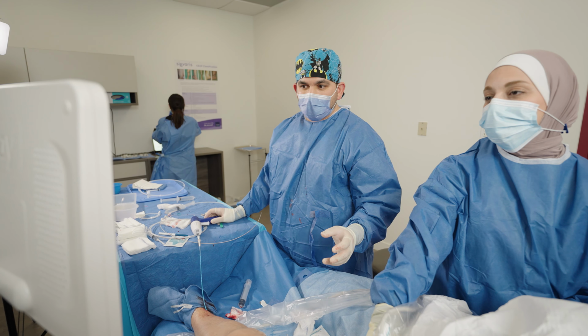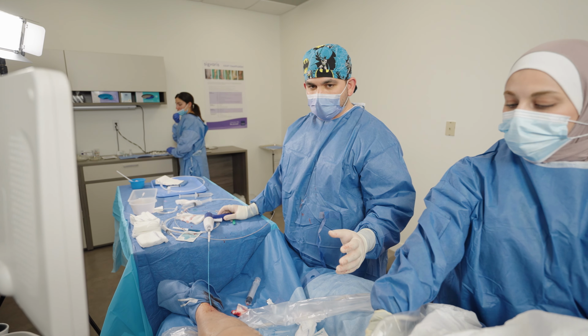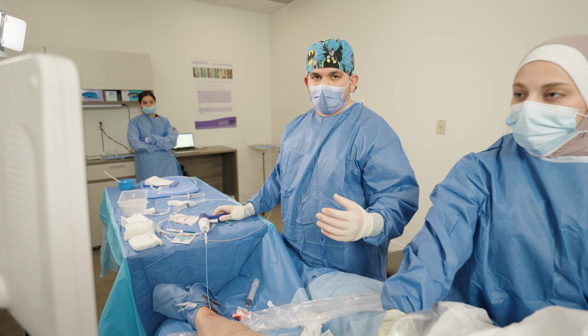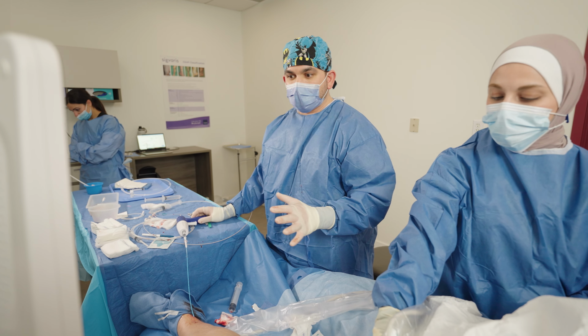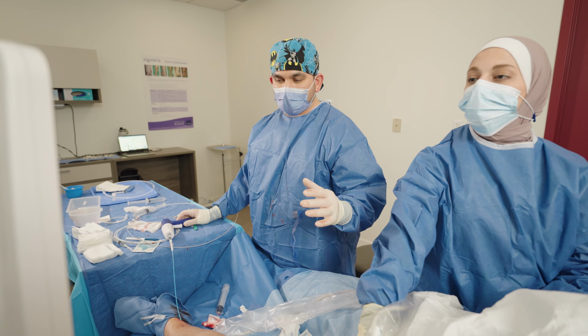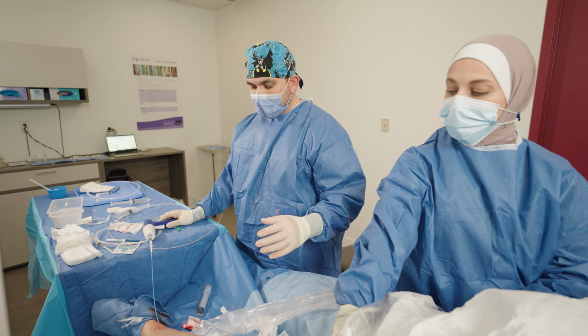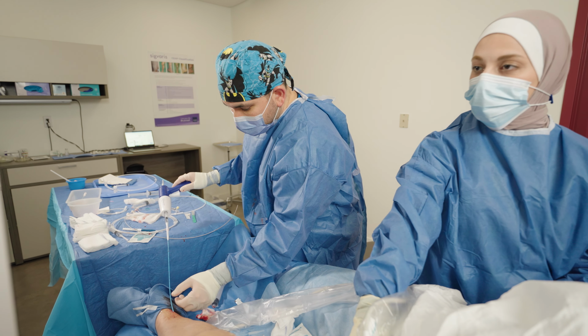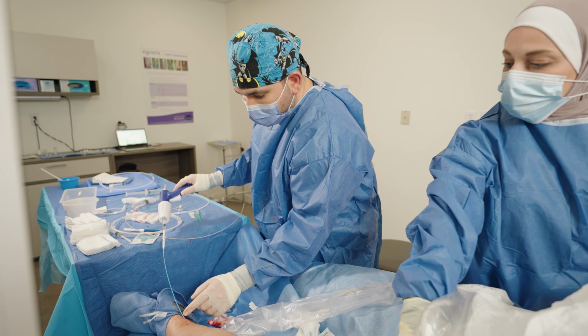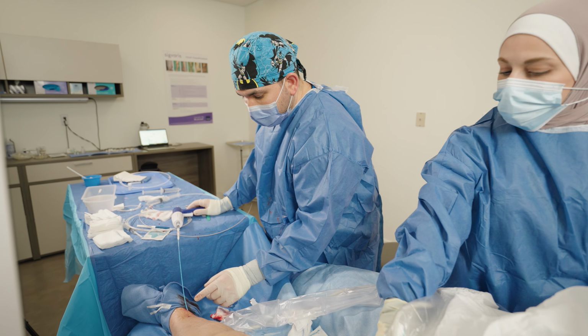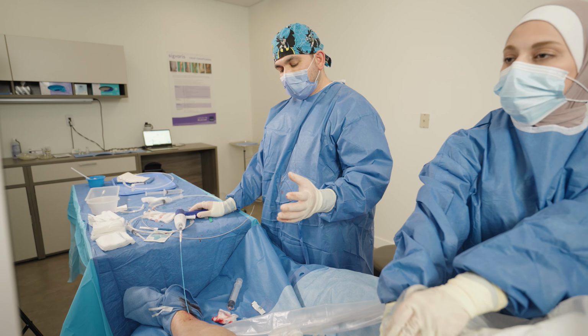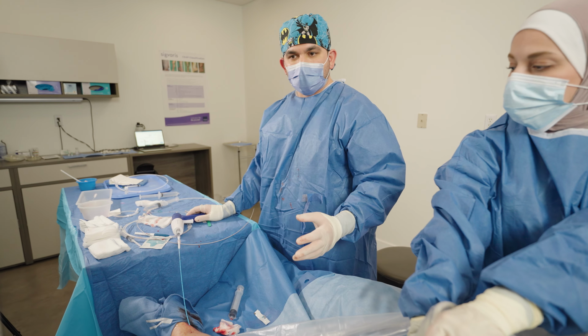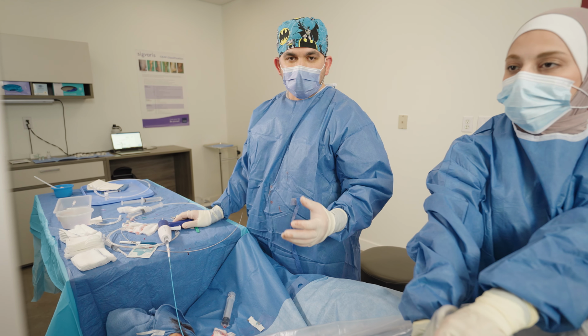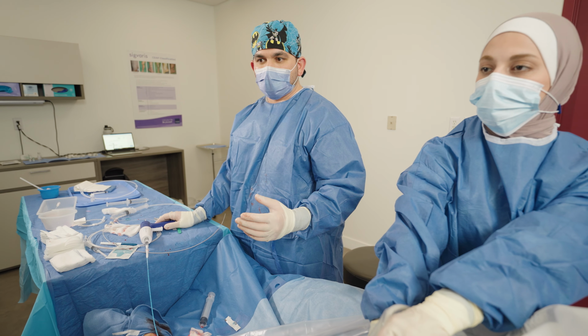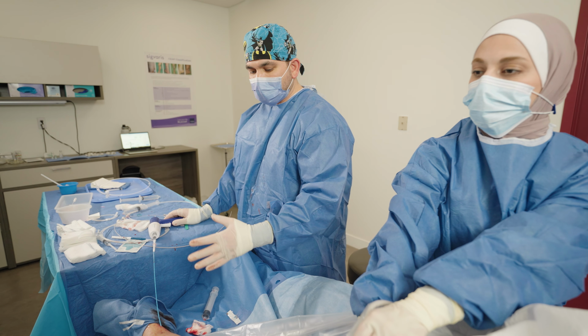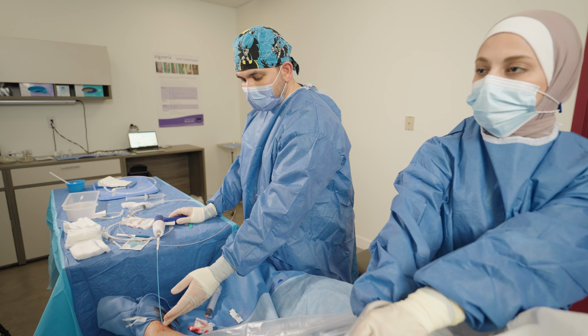So we've just delivered the first aliquot of the glue to seal off the saphenofemoral junction. Now you have to wait 3 minutes to safely allow the adhesive to polymerize in the blood vessel to prevent any dislodgement up into the deep veins or the more important veins. And then we mark our distances with these markers that come with the catheter. So each black dot is separated by 1 centimeter. And each time we deliver an aliquot of the glue, we move the actual sheath 3 centimeters back, inject, wait 30 seconds, move 3 centimeters back, inject, wait 30 seconds, so on and so forth until the entire vein is sealed to its entry point near the ankle here.